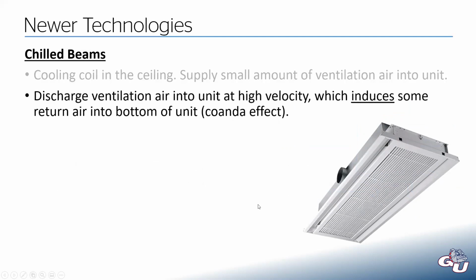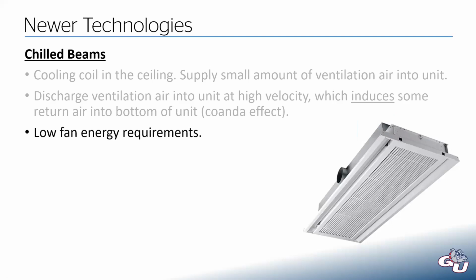And that ventilation air that's going into the unit is going in at a really high velocity, which is actually going to induce some return air into the bottom of the unit. I'll have a better image here in a second. One good thing about these is they have very low fan energy requirements, which I'll dive into in a sec. They also provide improved chiller efficiency.